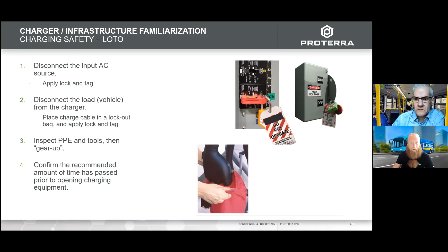Do your live-dead-live test. Check again against a known good voltage source, confirming the meter is live. Do your dead test, examining both the DC and AC sides of the circuit inside the charger, confirming the absence of voltage. Then do a live test again, going back to the known good voltage source, making sure you get the same or a very close reading as before.